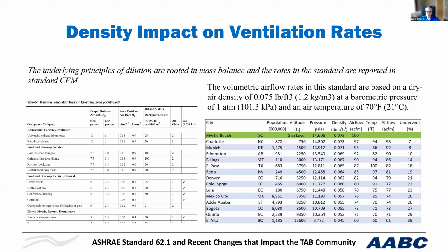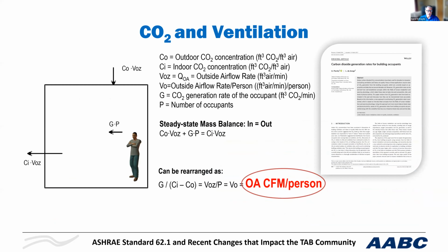It's about mass airflow and dilution. So I'm going to switch gears a little bit, even though we're still going to talk about mass airflow, because we're talking about another mass balance calculation, and that is CO2 DCV. CO2 DCV has existed and been allowed in the standard since 1989. However, there has been confusion about the appropriate level in the space to maintain since that time.